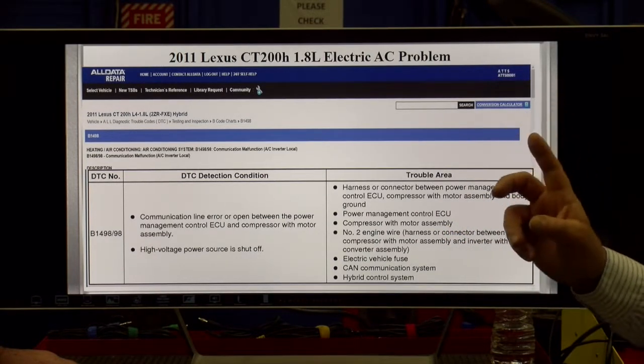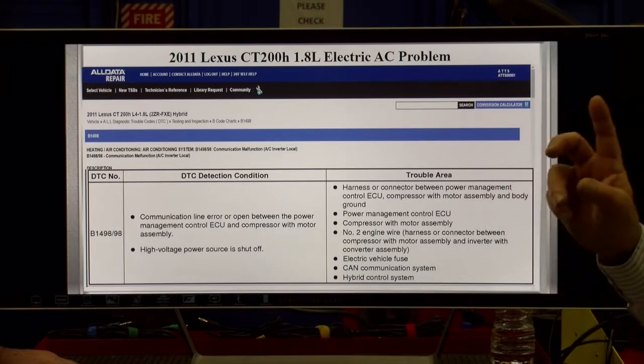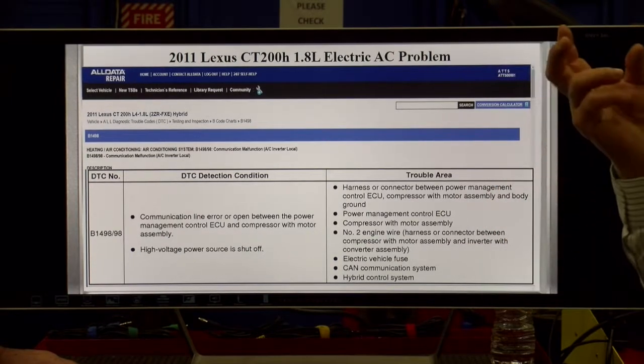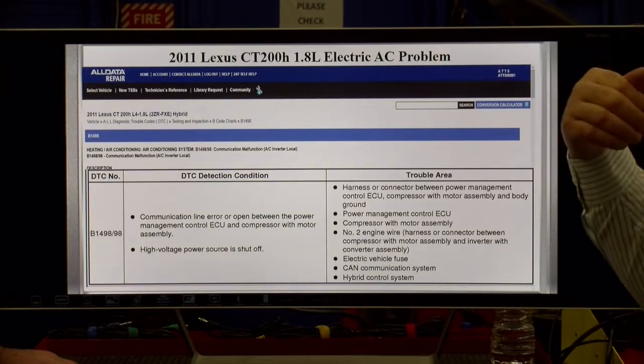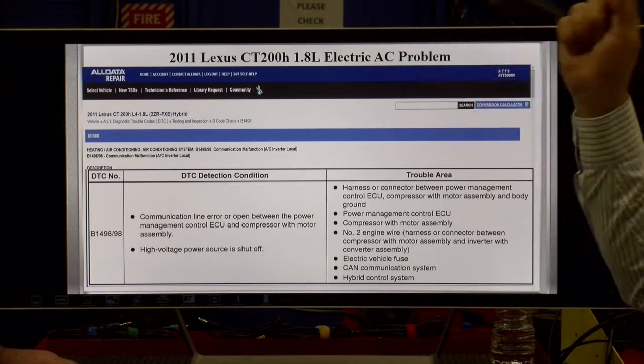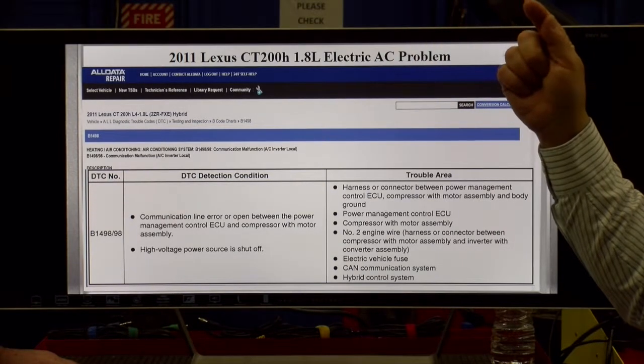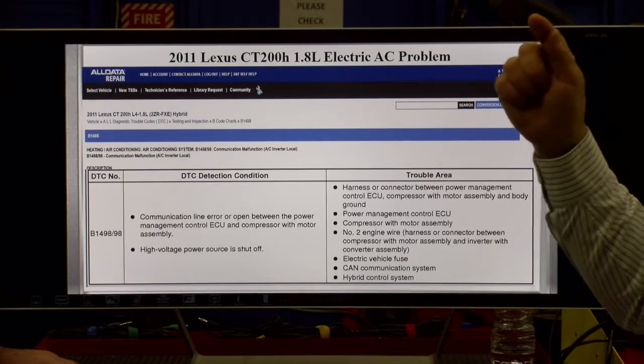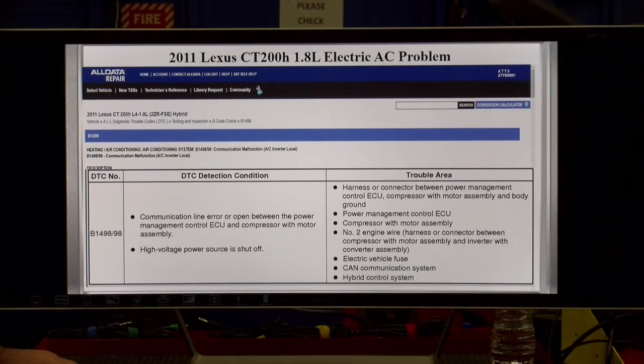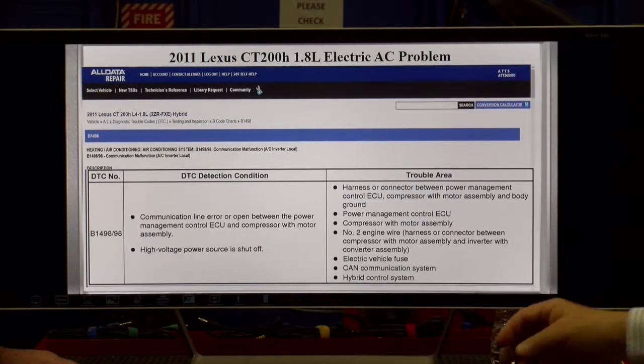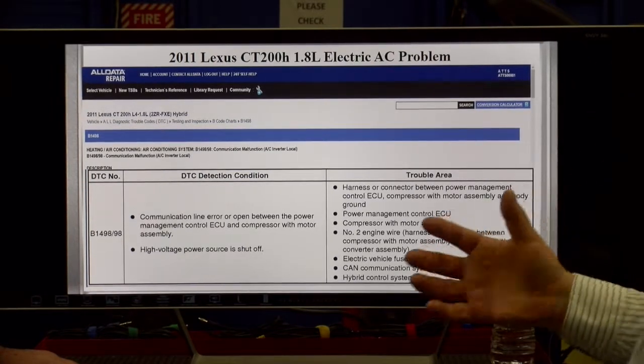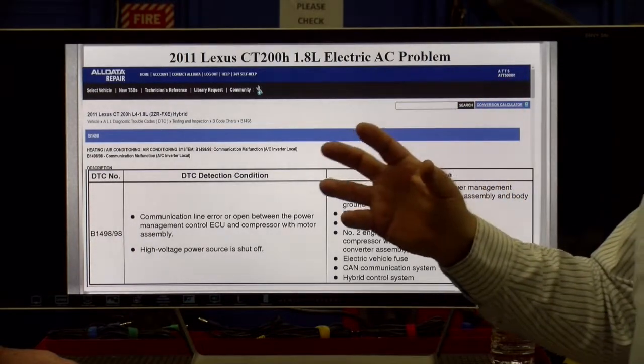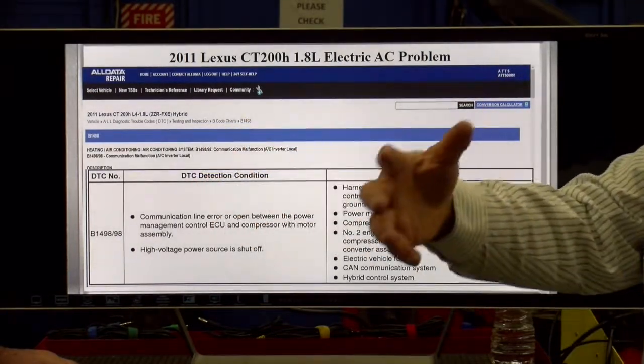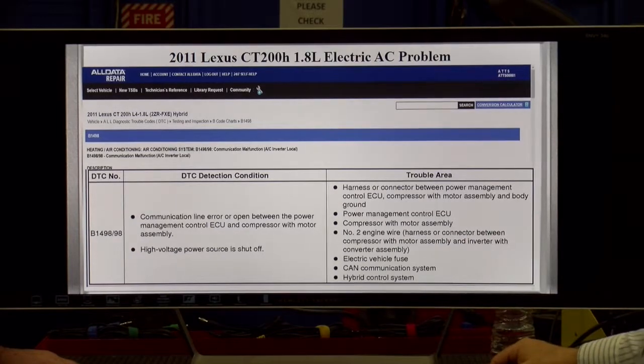And what we did, with high voltage gloves on, we unplugged, power off, plugged, power back on to see if we were getting power there. No power. So that tells me it's the wire going up or the inverter itself, okay? And of course, the guy doesn't want to spend the money, but he complained because we had a 72-degree day the other day, and he didn't have air conditioning. Probably would force them to come in.